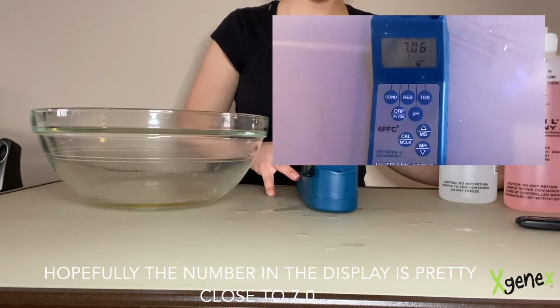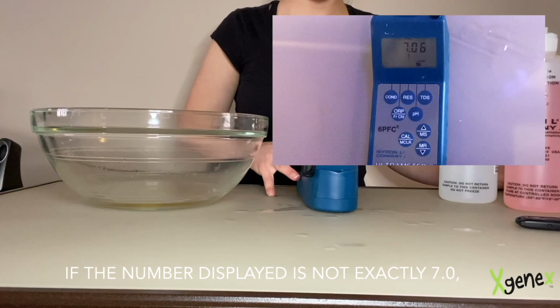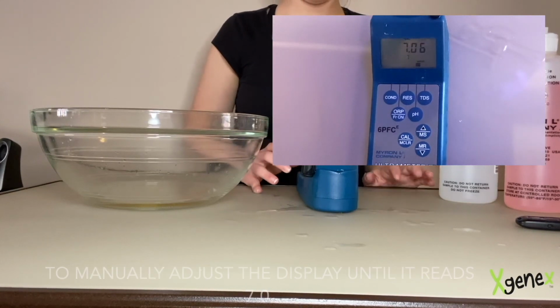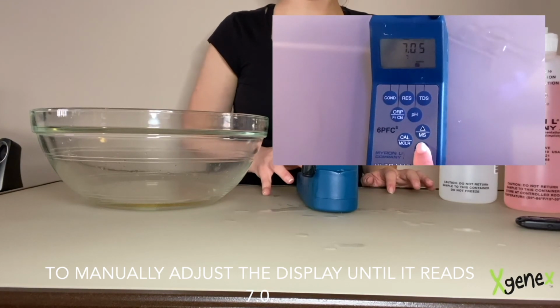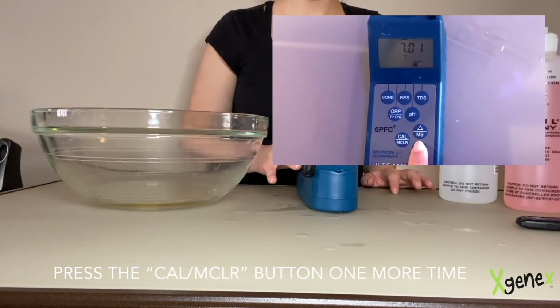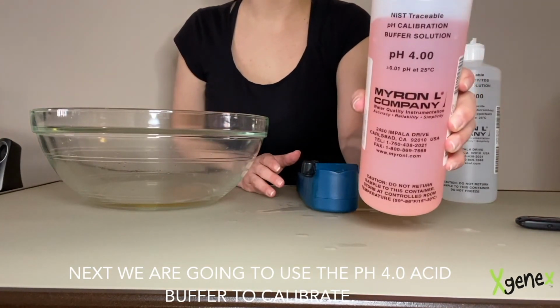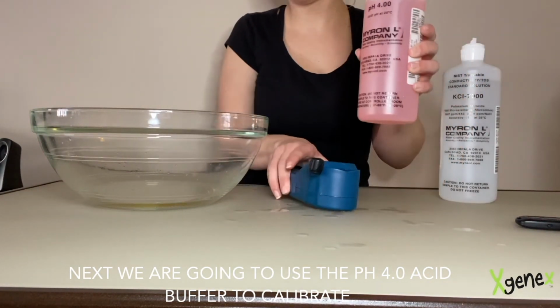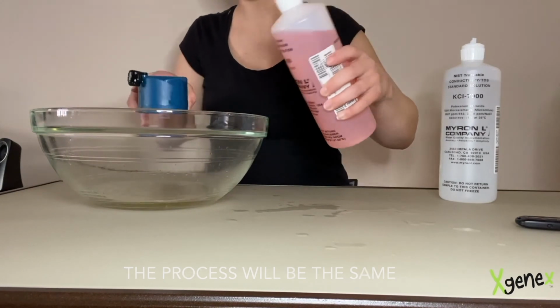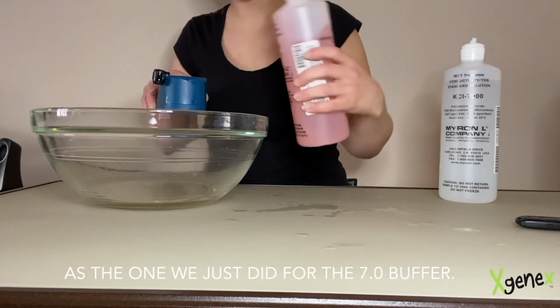Hopefully the number in the display is pretty close to 7.0. If the number displayed is not exactly 7.0, use the up-down arrow buttons to manually adjust the display until it reads 7.0. Press the Cal button one more time to accept the adjustment when finished. Next, we are going to use the pH 4.0 acid buffer to calibrate. The process will be the same as the one we just did for the 7.0 buffer.